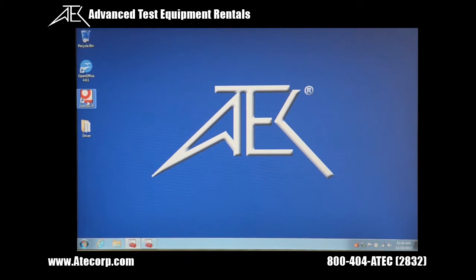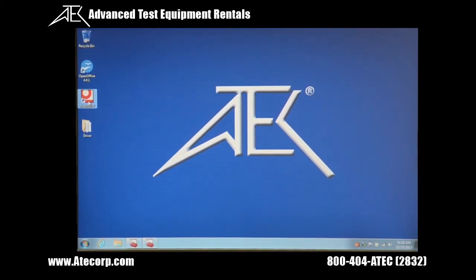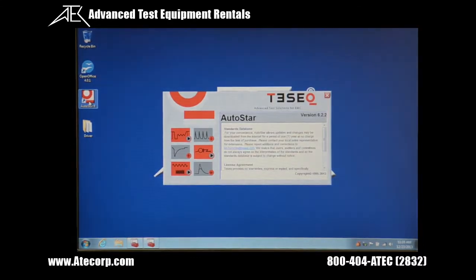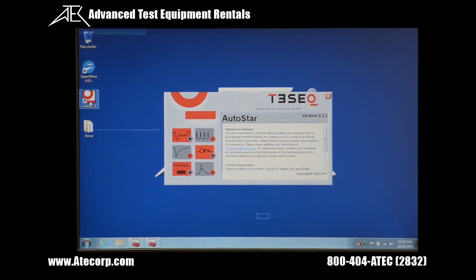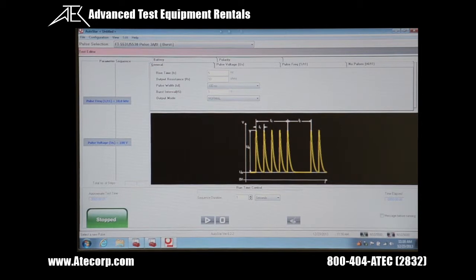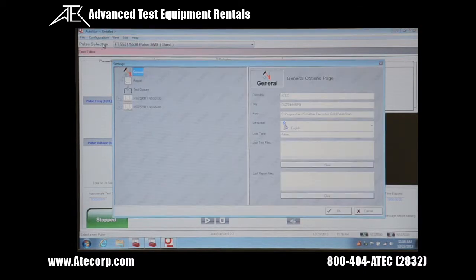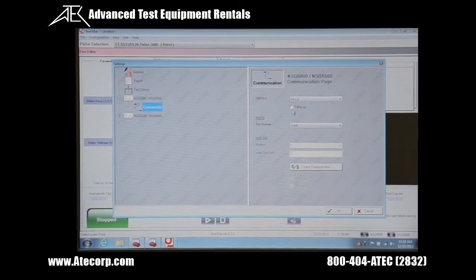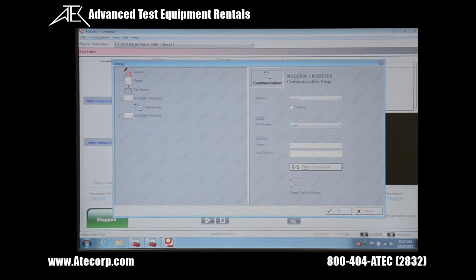Once you've noted the port, open the AutoStar program. Once the program opens up, go to the upper section, select Configurations, then go to Settings, and go to the NSG 5000, NSG 5500. Select the plus and you'll see Communications. Select Communications. You'll see that you're set up for RS232 COM 4, which is the way that it's set up with the USB cable. Do a Communications check — all communications passed. The program's ready to run.